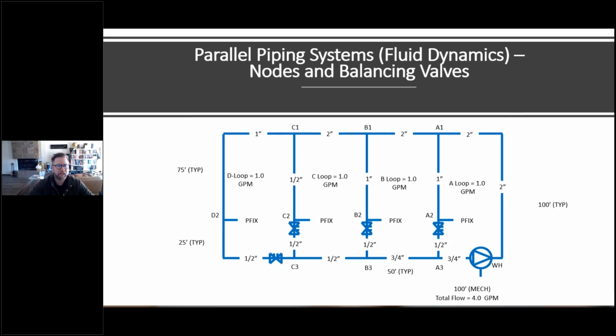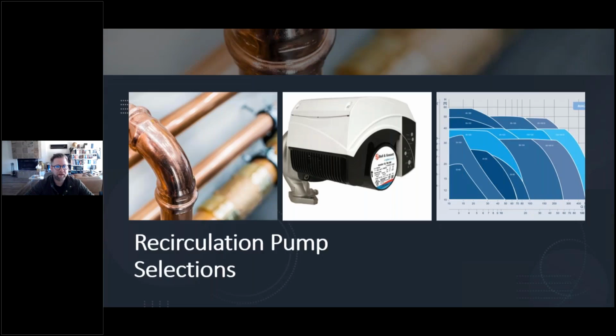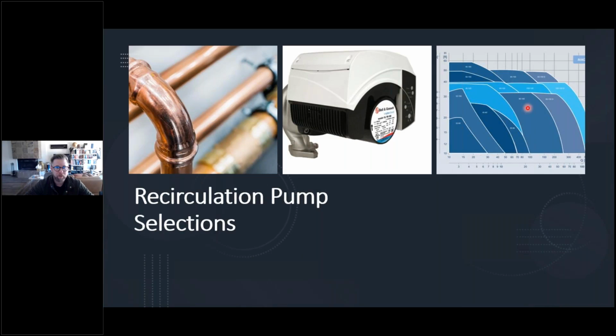So it's important when selecting a pump that we look at the pump curves and make sure that our point in our system is below the curve. I cannot tell you how many times I did quality control on projects and the plumbing designer would have selected this pump, but their system was out here. That's never going to work. What's going to happen is the pump is going to go probably back to this range, and it's going to try to shoot for almost no flow and almost deadheading, more likely than not. Or you're going to burn it out because it keeps trying to hunt for that furthest point. So you need to make sure your point is inside the curve.